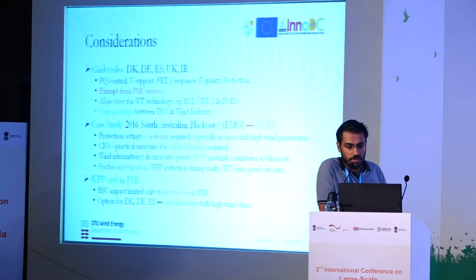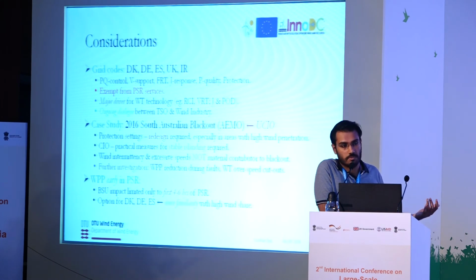And some important points. Currently, the grid codes of mainly countries that have more experience dealing with large wind penetration, offshore wind penetration, do provide technical requirements of connection of wind turbines at the HV and the EHV level for PQ control, voltage support, inertial response, protection, and fault ride through. However, there is exemption from power system restoration services. Now, grid codes have been a major driver for wind turbine technology in the past. For example, recently, reactive current injection and inertia and power oscillation damping is quite a good example. And therefore, an ongoing dialogue between the wind industry and the transmission system operator is very essential to make this a reality.